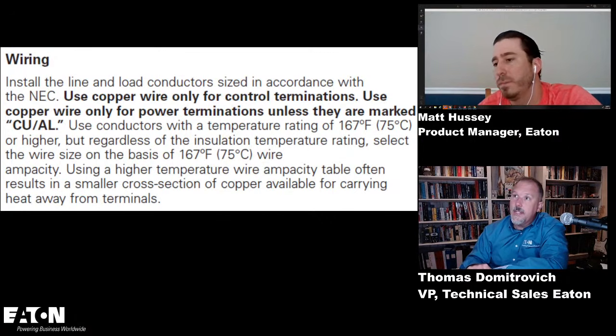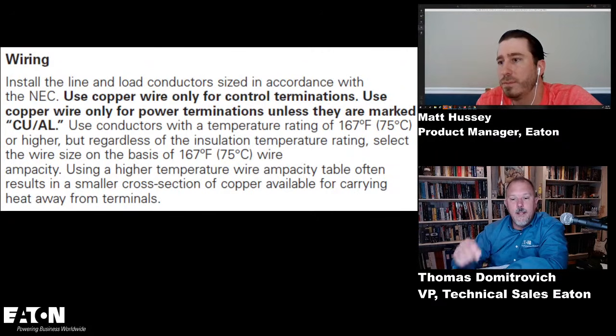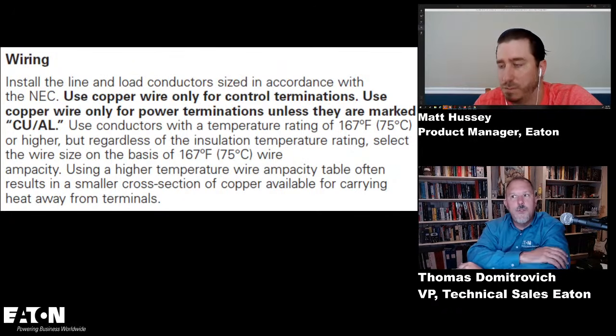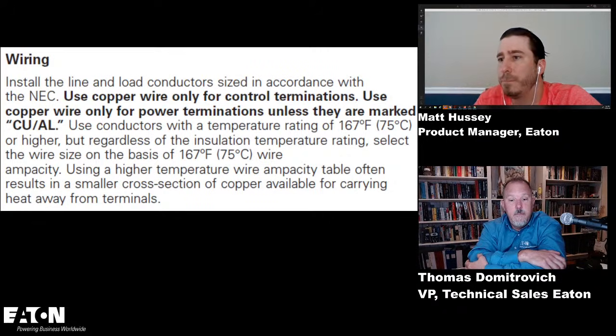All right, so I'm looking at our instruction book, and it says install the line and load conductors sized in accordance with the NEC. Here, I saw this was interesting. It says use copper wire only for control terminations. So I can't use copper clad aluminum or anything like that. Yep. I meant to check on this in the standard. Is that something specific to our installation, or is that driven by the standard? I'm not sure.